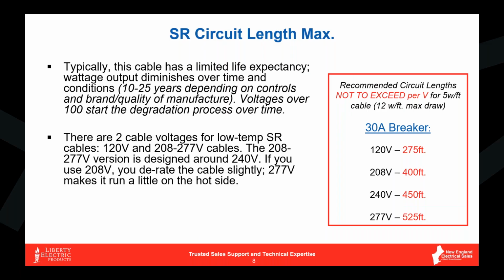commercial industrial grade heat trace cable, depending on its use, its voltage, and its quality of manufacture, can typically last anywhere from about 10 to 25 years. So there is, again, some separation in quality. And I can at least speak from this perspective that heat cable is generally one of those things where you get what you pay for.